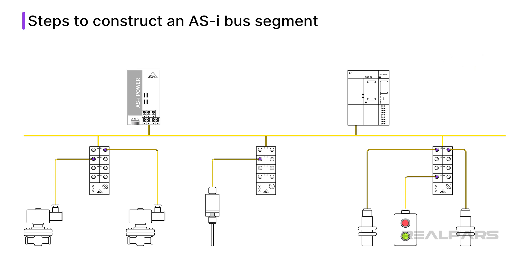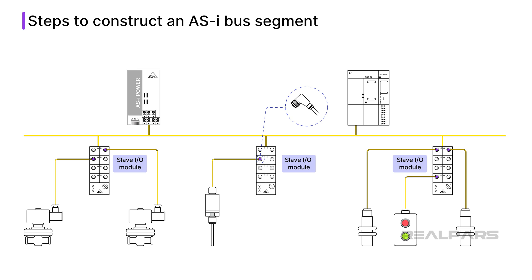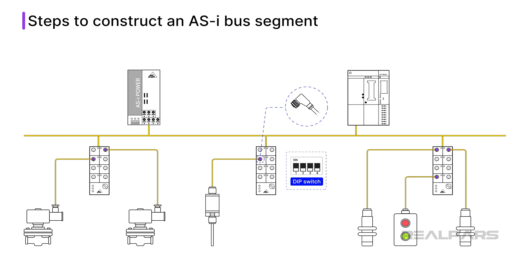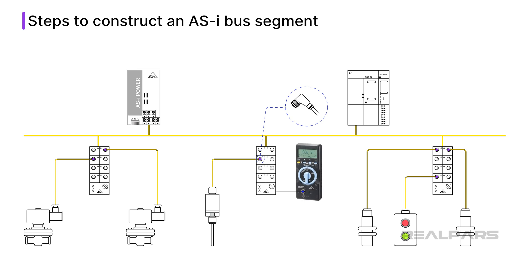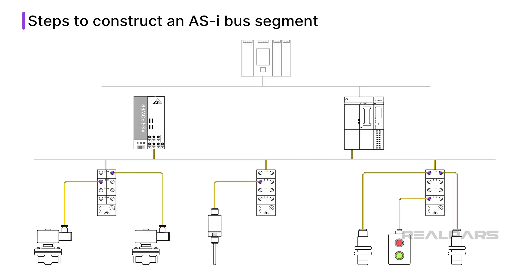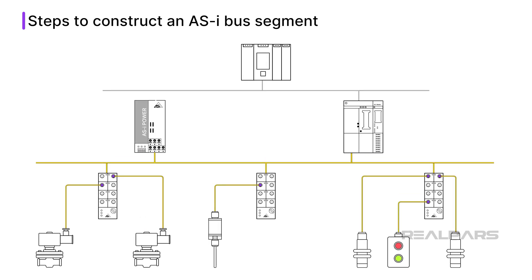Now, I will install each slave device using an appropriate connector. Each slave needs to have its unique segment address set at the device. Sometimes this can be done with DIP switches or rotary switches. Often a special handheld communicator must be used to set the node address. With the cabling to the field devices completed, I make the final connection at the master communication card.